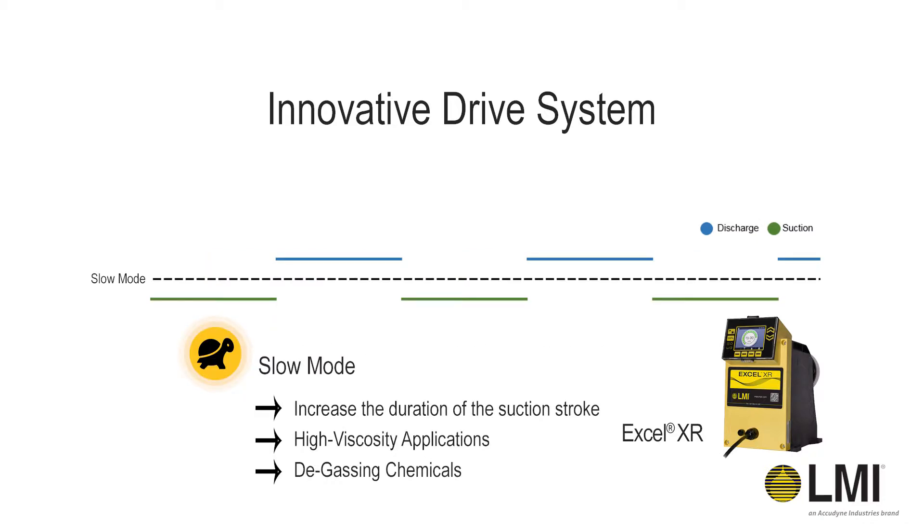In applications where chemicals are sensitive to suction stroke speed, the Excel XR Pump can engage slow mode, which will slow down the suction stroke of the pump. This is a big advantage in applications that utilize high-viscosity chemicals or degassing chemicals such as peracetic acid.